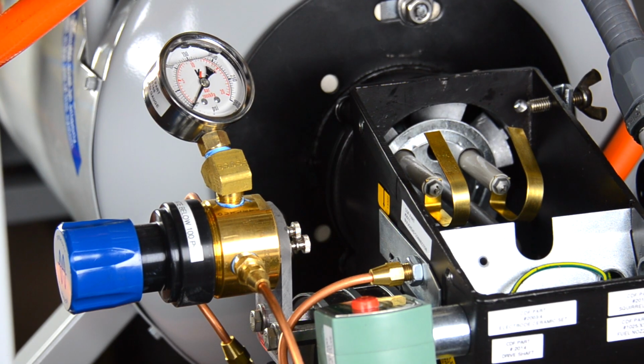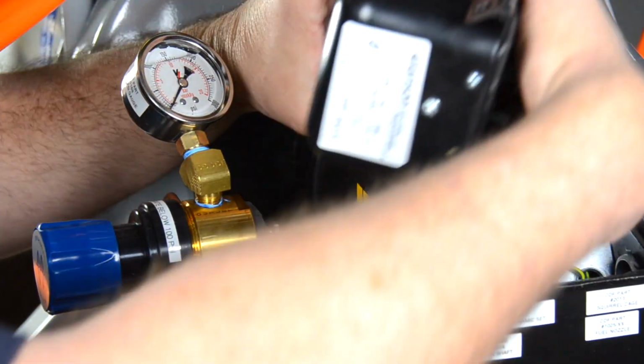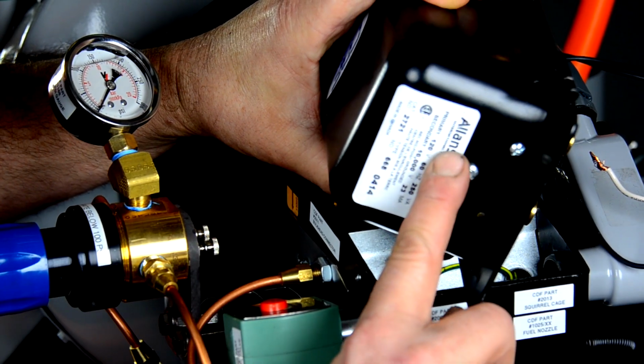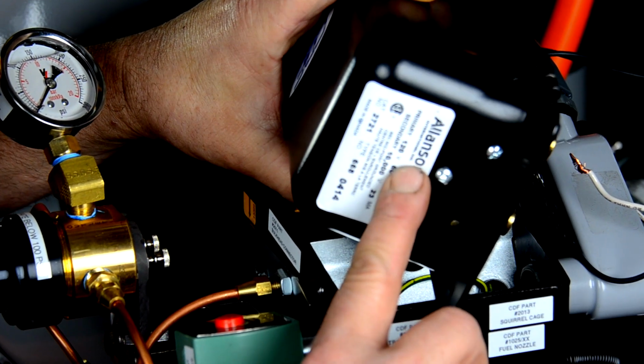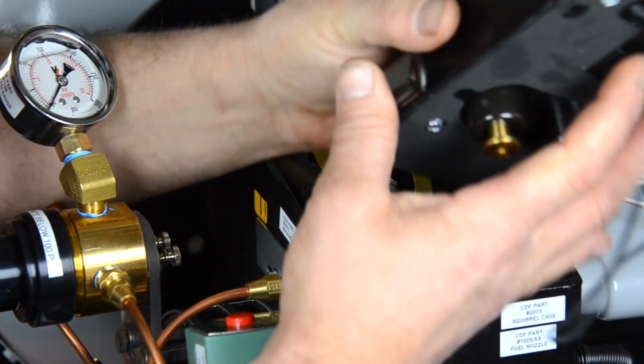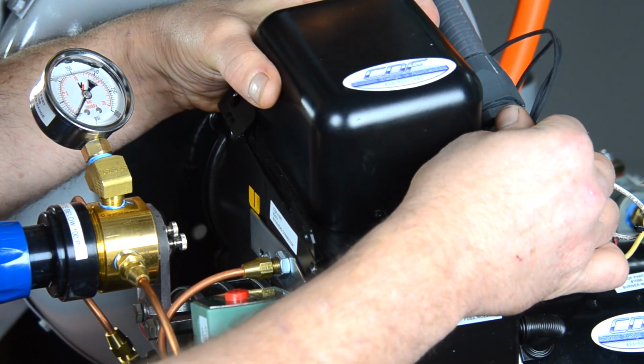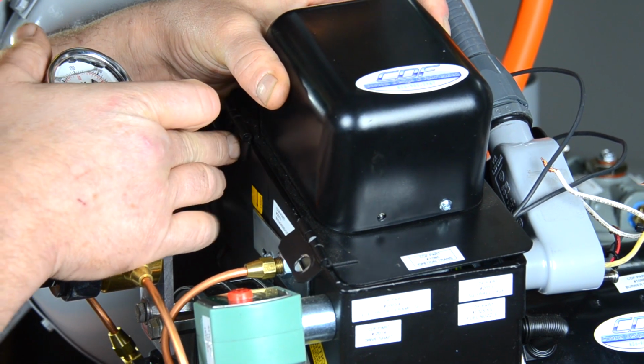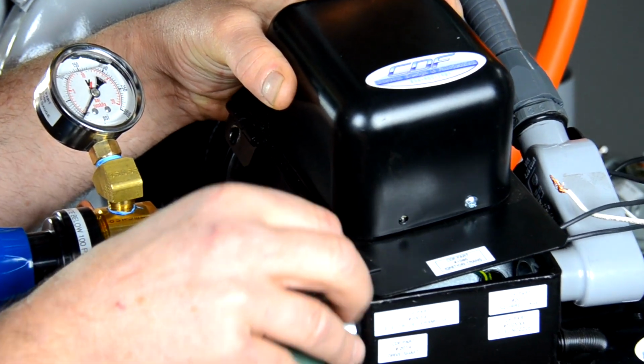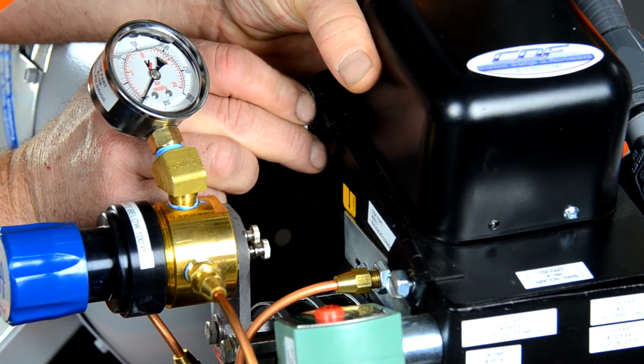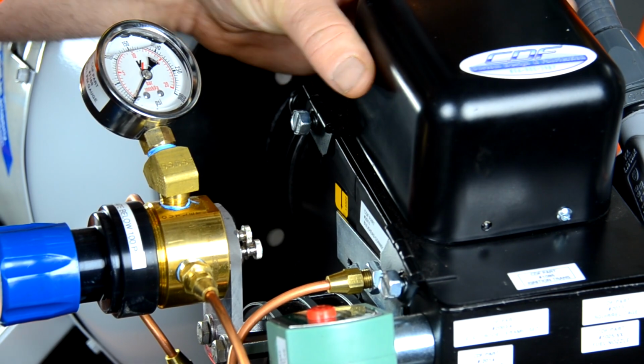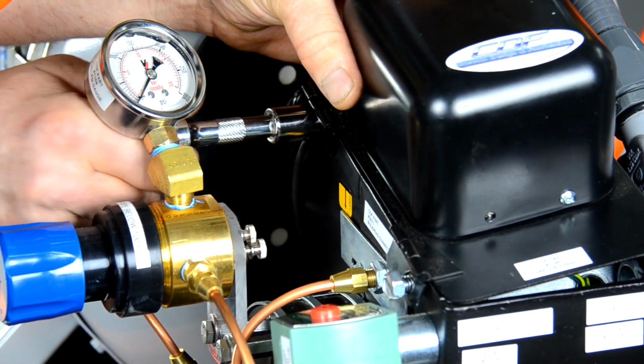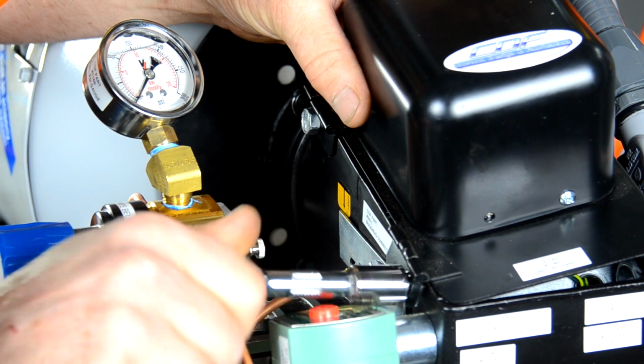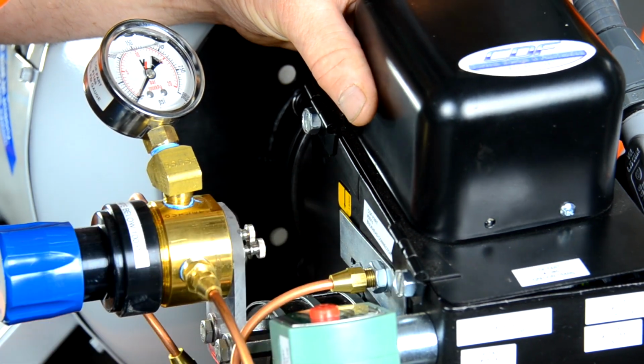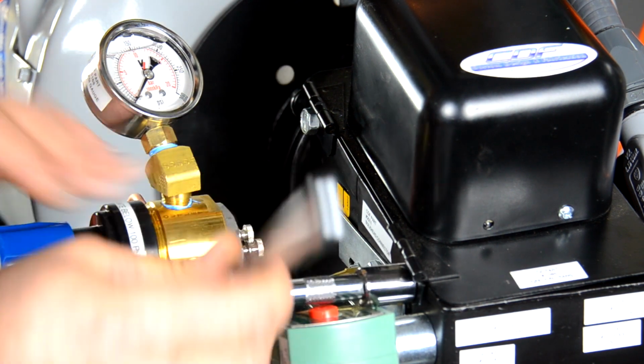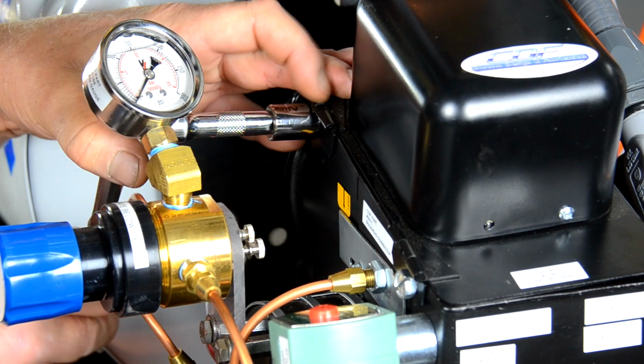Alright, now we're going to take a new transformer. Always check the voltage. Make sure that you have the correct voltage for the unit you're running. We have a primary voltage of 120, 60 cycle. That's what you need for this system. Careful not to pinch your wires on the other side. And line up your hinges and put your screws back in. You just want to snug them up, don't over tighten them.